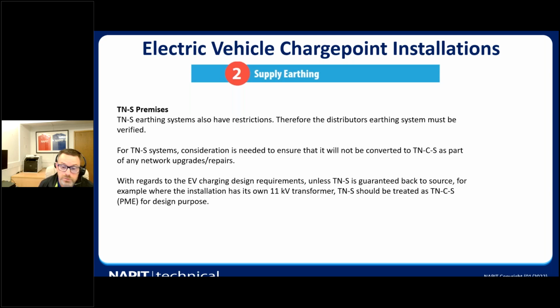So TN-S systems for EV charge points and for other things should be treated as TN-C-S for design purposes, because we can't confirm the TN-S system back to the source unless the distributor or supplier can confirm that, and it's very difficult for them to do it because as repairs are carried out, they've replaced the cables from TN-S to TN-C-S cables for installation purposes.